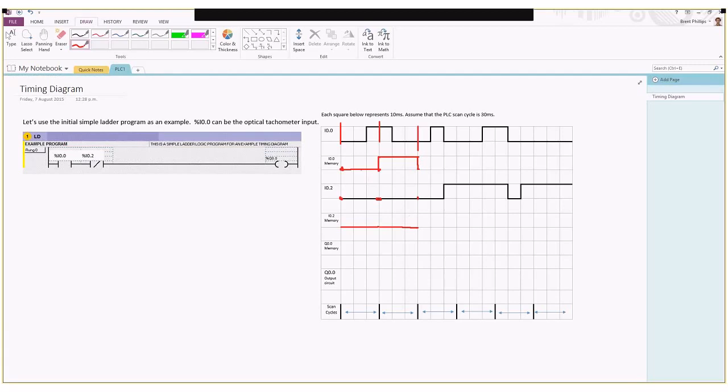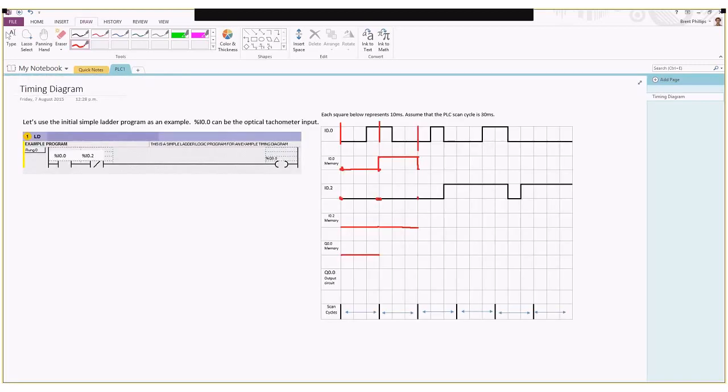Now that we've got these values in the memory, these are the ones that the PLC uses when it's solving the logic to find out what's going on with the output. If we look at the logic we've got on the left side, we say if our input zero is on and if input two is off, then it gives us the logic to turn on our output. In our first section, this first bit of time, we've got both of our inputs being off so that's going to make our output stay off as well.